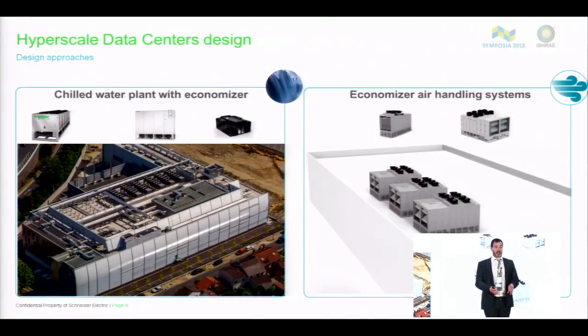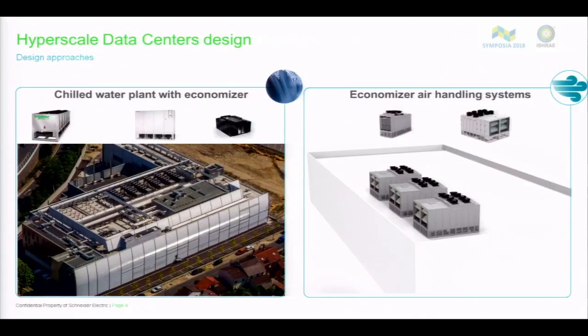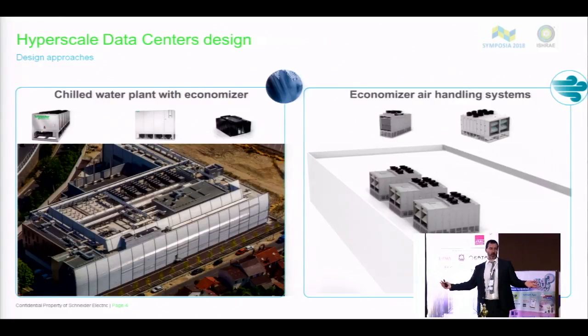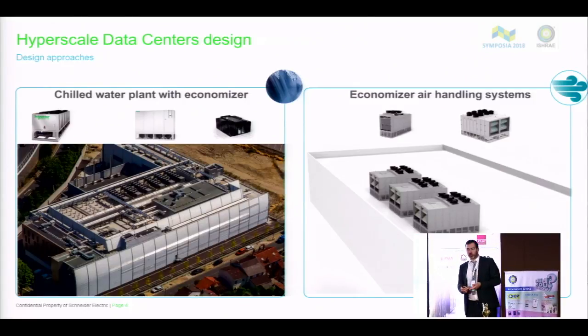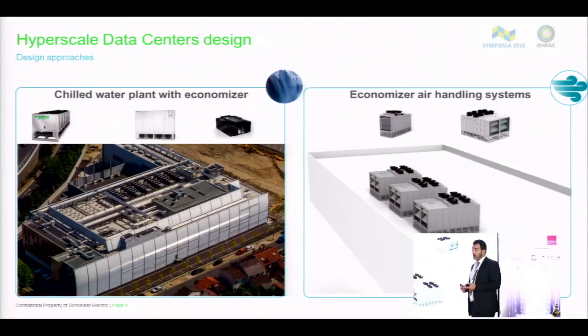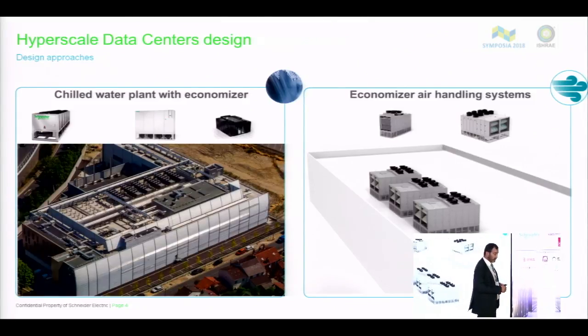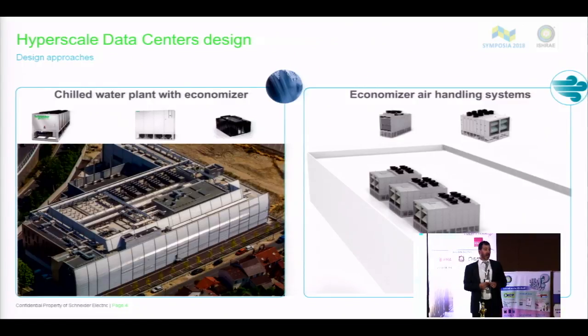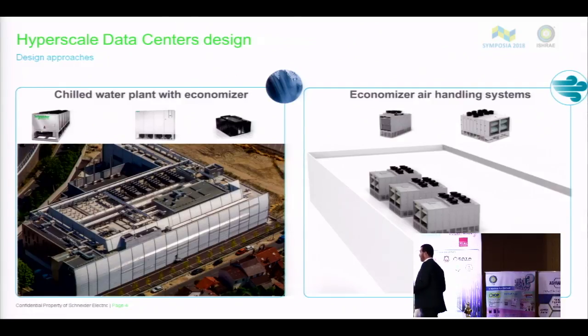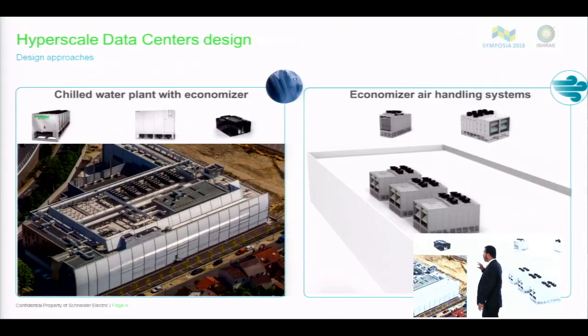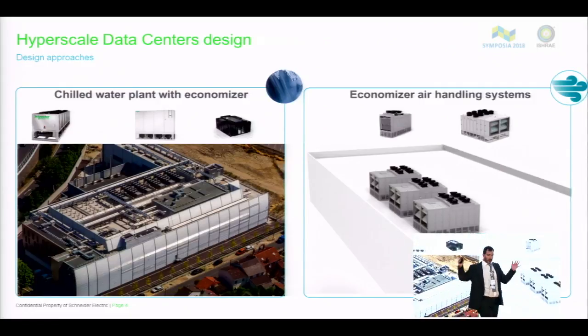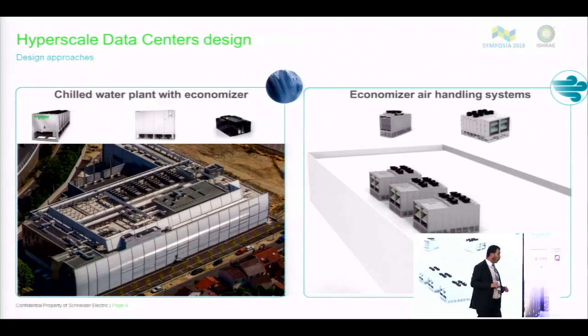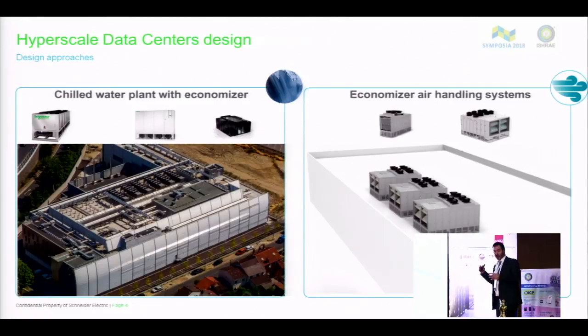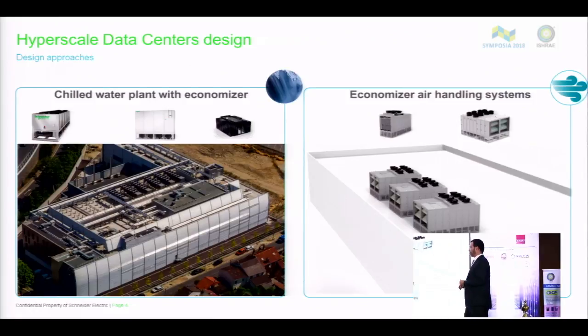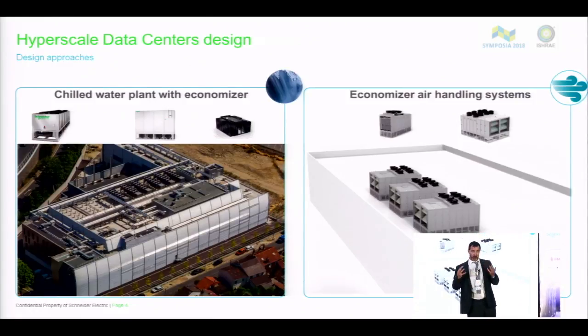Starting from a simple fact. When we design a large data center, in the cooling infrastructure there are three solutions at the end of the day. Air conditioning unit, CRAC, based on refrigerant. CRAH based on chilled water connected to a chiller. And air handling unit. In large data centers, more and more the large and hyperscale data centers are based on either a chilled water system, so CRAH connected to a chiller, or on the air economizer, so the air handler. Those are the two technologies that in the most recent years are moving into the large designs.